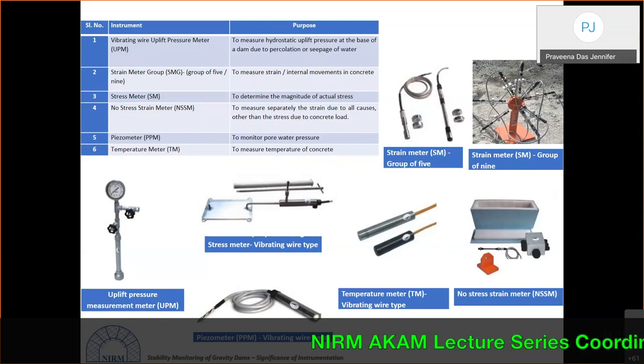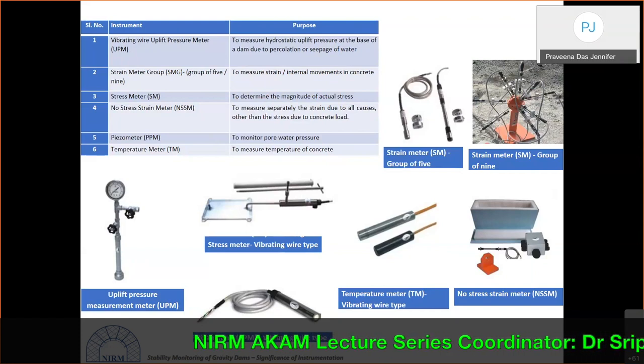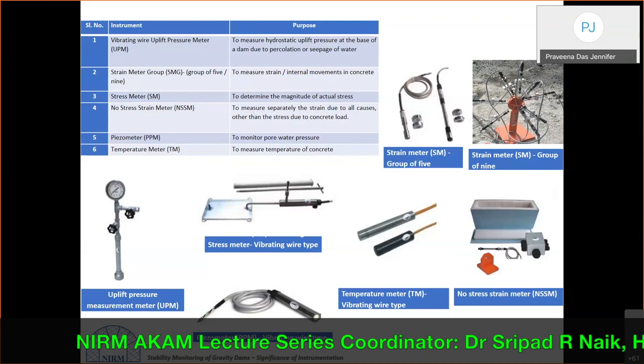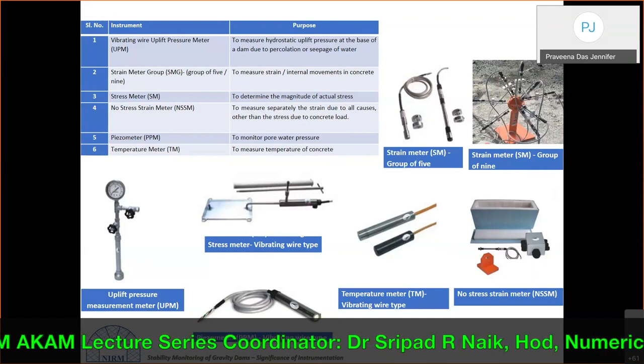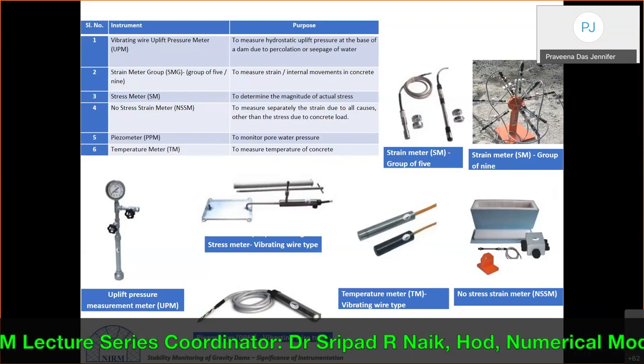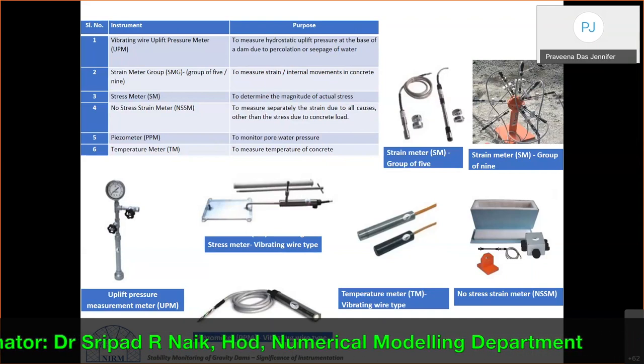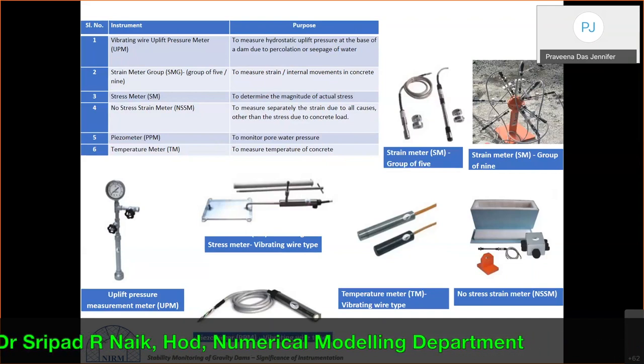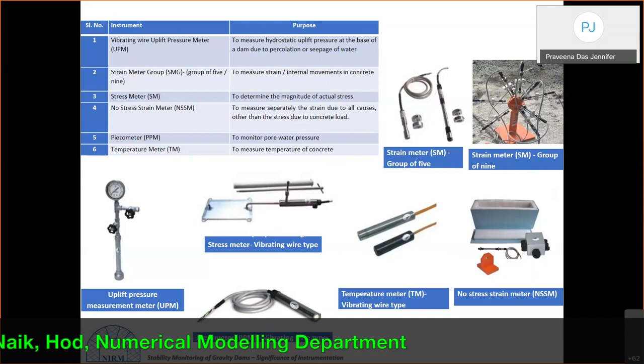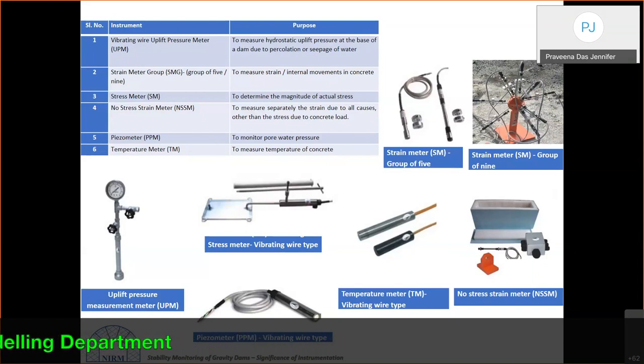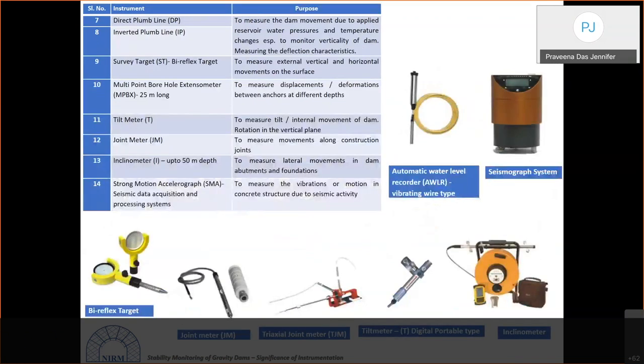Stress meters measure the magnitude of stress accumulated within the dam body. No-stress strain meters separate strain due to all causes other than concrete loading. Piezometers monitor pore water pressure acting on the dam body, and temperature meters serve as an essential monitoring parameter.